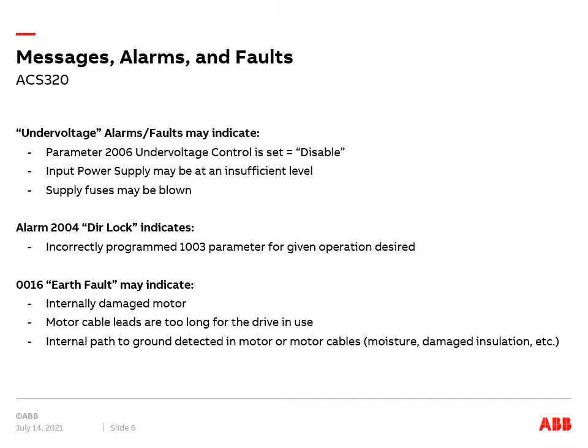Undervoltages occur when fuses are blown on the line side of the drive. They can also be caused by a bad transformer or other reduced supply network voltage level. Alarm 2004, Direction Lock, occurs when parameter 1003 is programmed incorrectly.